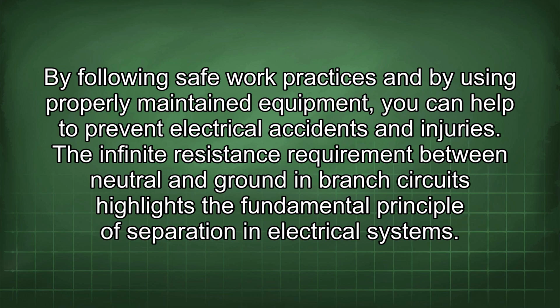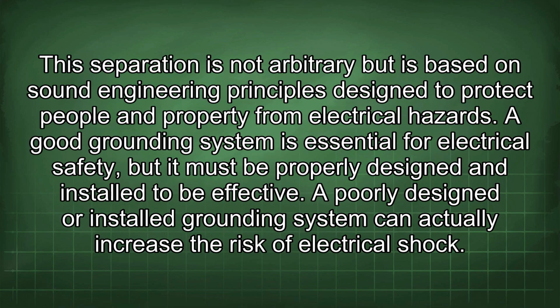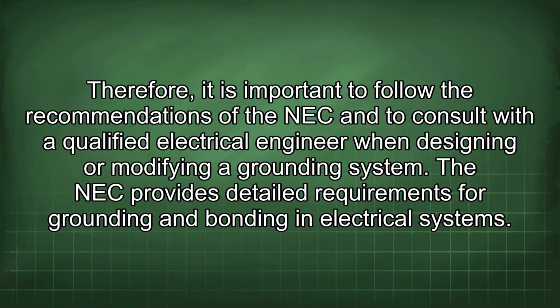The infinite resistance requirement between neutral and ground in branch circuits highlights the fundamental principle of separation in electrical systems. This separation is not arbitrary, but is based on sound engineering principles designed to protect people and property from electrical hazard. A good grounding system is essential for electrical safety, but it must be properly designed and installed to be effective. A poorly designed or installed grounding system can actually increase the risk of electrical shock. Therefore, it is important to follow the recommendations of the NEC and to consult with a qualified electrical engineer when designing or modifying a grounding system.